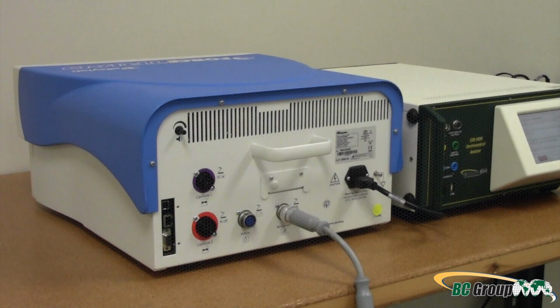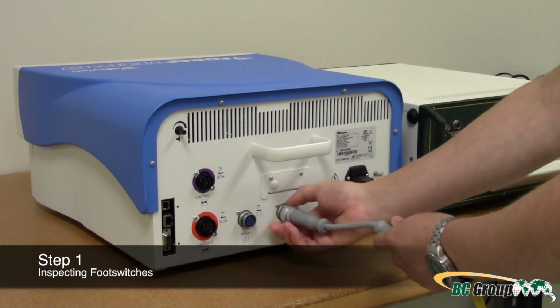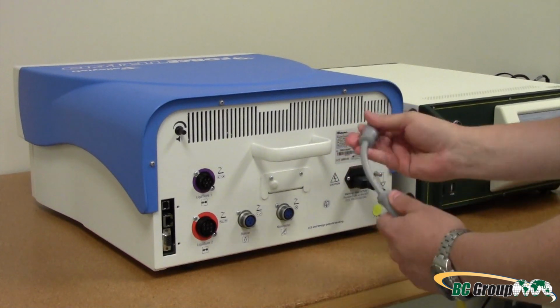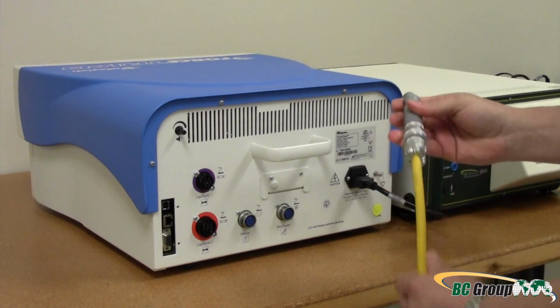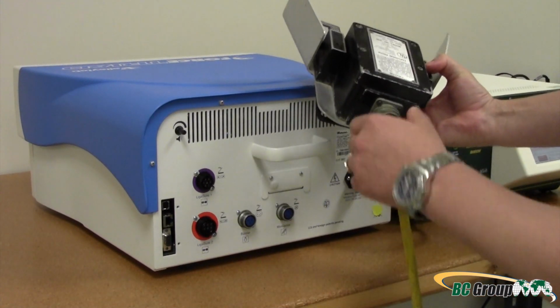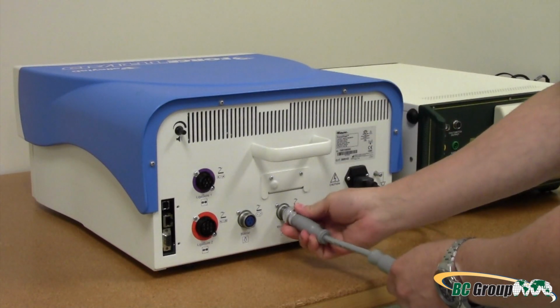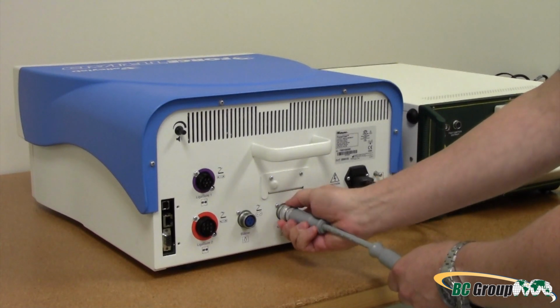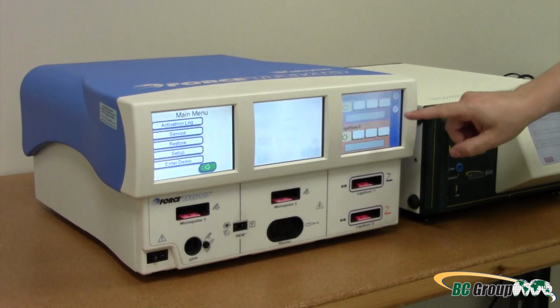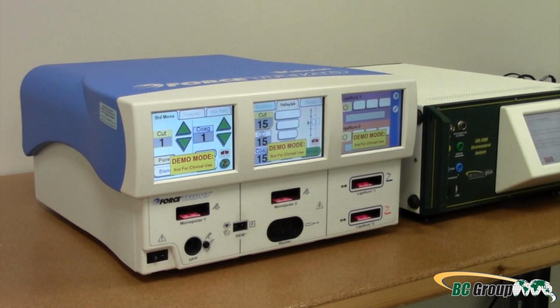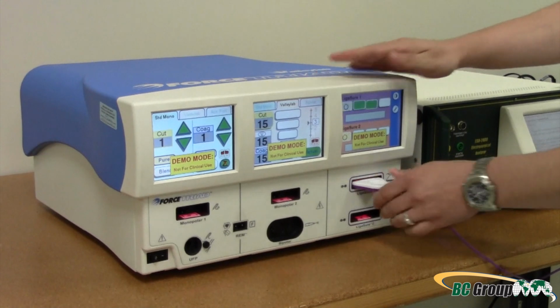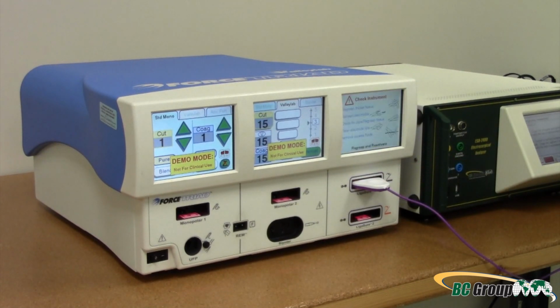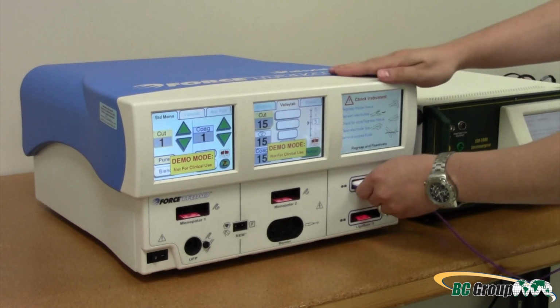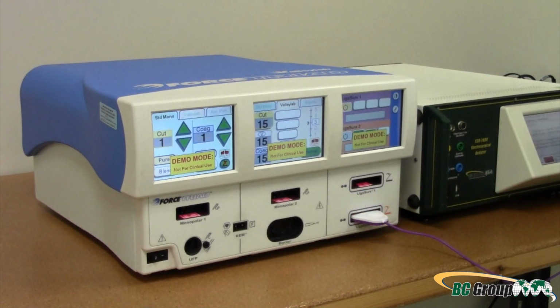Physical inspections. Step 1. Inspecting the foot switches. Remove foot switches. Inspect connectors for damage or corrosion. Inspect foot switches for damage. Reconnect the foot switches. Enter Demo mode by pressing the wrench icon and then Enter Demo. Trigger monopolar and bipolar foot switches to verify acknowledgement. Connect a LigaSure handpiece to the LigaSure 1 port. Trigger the handpiece and verify acknowledgement. Connect a LigaSure handpiece to the LigaSure 2 port. Trigger the handpiece and verify acknowledgement.